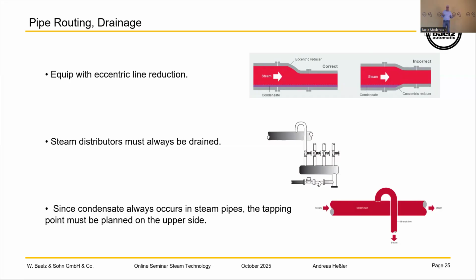And the next one: when you have water inside the steam and you want to tap a point off the steam, the take-off from the steam pipe always has to be on the top, because then you can be sure that you do not take the water with the steam.